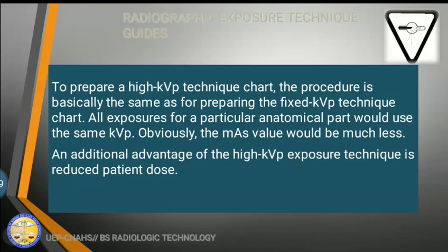So to prepare a high KVP technique chart, the procedure is basically the same as for preparing the fixed KVP technique chart. So all exposures for a particular anatomical part would use the same KVP, and obviously the MAS would be much less.